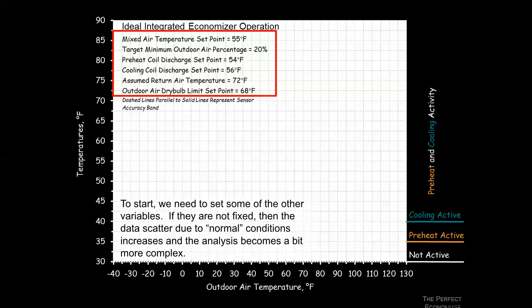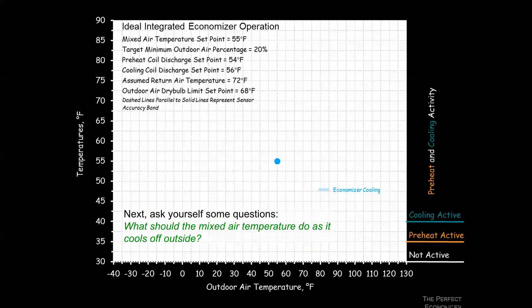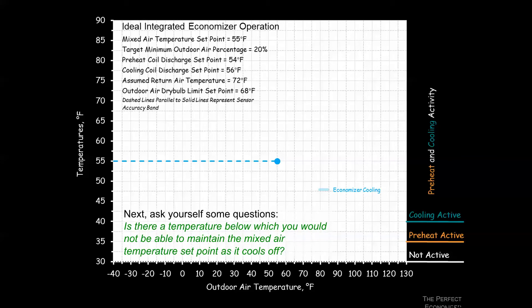When it's 55 degrees outside, we expect the mixed air temperature to be 55 degrees — we just pass that right through. When it's colder, the economizer dampers modulate to continue hitting 55 degrees in the mixed air plenum. But at some point it gets cold enough that we must maintain minimum ventilation and can no longer hold that 55-degree set point.